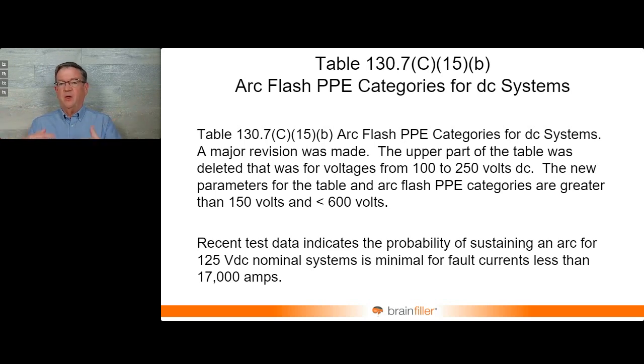So you start having lower voltages. That makes it more difficult. And the fault current, that results in the plasma, the ionizing air, which is conducting. And so if you have a more limited fault current, that makes it a little more difficult to sustain as well. This is not IEEE data.